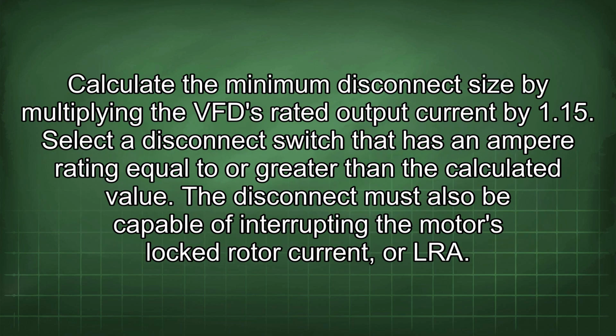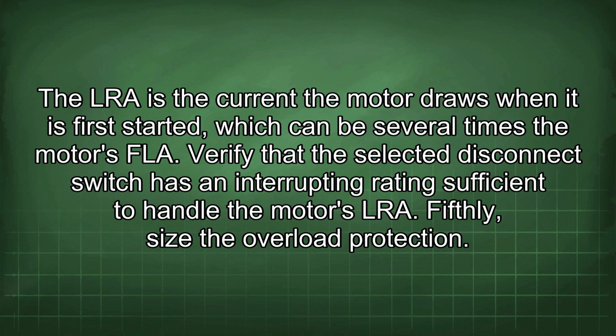Calculate the minimum disconnect size by multiplying the VFD rated output current by 1.15. Select a disconnect switch that has an ampere rating equal to or greater than the calculated value. The disconnect must also be capable of interrupting the motor's locked rotor current, or LRA. The LRA is the current the motor draws when it is first started, which can be several times the motor's FLA. Verify that the selected disconnect switch has an interrupting rating sufficient to handle the motor's LRA.